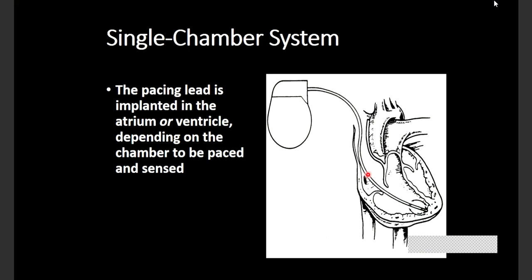And another lead problem would be an insulation problem. Whatever electricity the battery generates should go through the lead alone and should exit from the tip. So whatever flow of electrons there is should exit from the tip. To make sure that it exits only through the tip, the entire lead is insulated. The insulation makes sure that whatever electrons the battery generates come through only the tip. Suppose you have an insulation failure, the surrounding insulation fails, then the electrons can easily exit out into the RA, into the RV. So again, whatever electricity you're generating doesn't actually reach the tip, because the electrons find an easy way out. There's no resistance to the flow of electrons. So in this case, you'll have battery depletion very early because the impedance drops to a great extent. And that's another reason why a battery would deplete early and you would find a pacemaker problem.